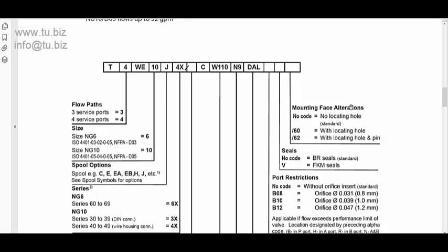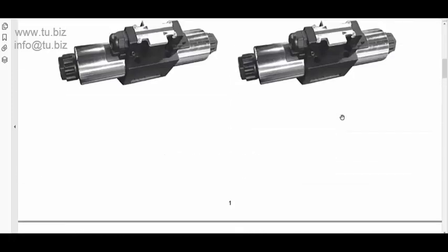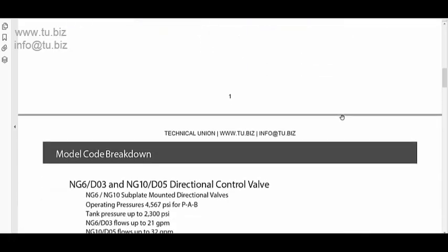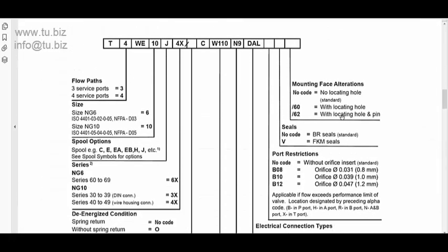So, if you're changing solenoid too often on these valves, I will look into filtering the oil to a good ISO level, contamination level, and you should have a better life, not just of the valves, but of your entire hydraulic system.